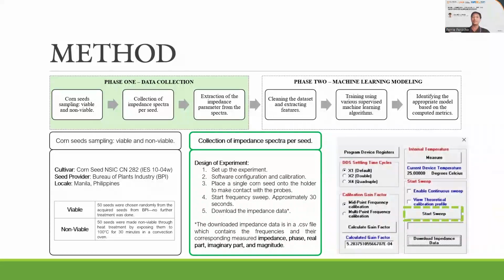Then start the frequency sweep by clicking the Start Sweep button. The frequency sweep takes around 30 seconds. After approximately 30 seconds, the impedance spectra will be available to download in a .csv file by clicking the Download Impedance Data button. The downloaded impedance data contains the frequency and their corresponding measured impedance, phase, real part, imaginary part, and magnitude.